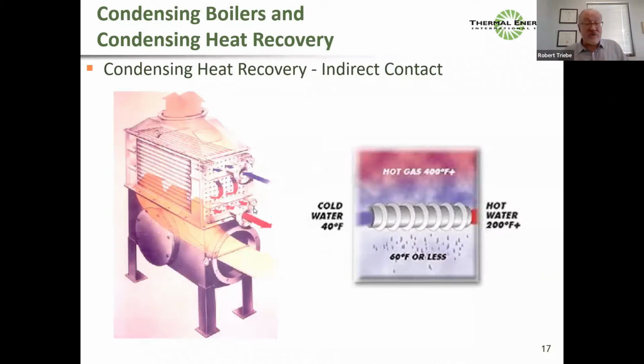And now we're just looking at the same things without a burner. So the economizers, a condensing heat recovery indirect contact economizer, is just the tubes from that indirect boiler, but you don't have a flame, you're just using waste heat. So it's just fin tubes really. Typically you could put in cold water at 40, you could cool the flue gas to 60 degrees or less. And the most common is that these are stainless steel with aluminum tubes. They're manufactured by a number of people, but it's the same concept.